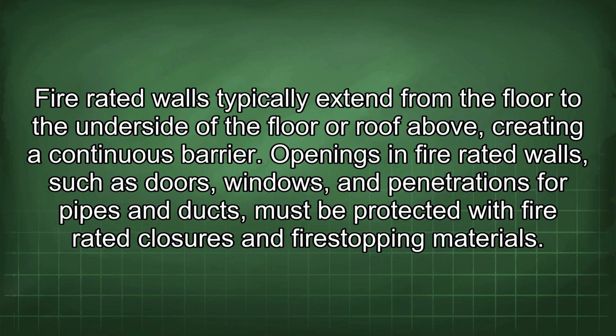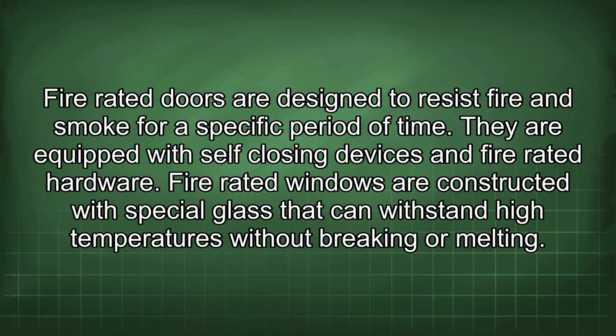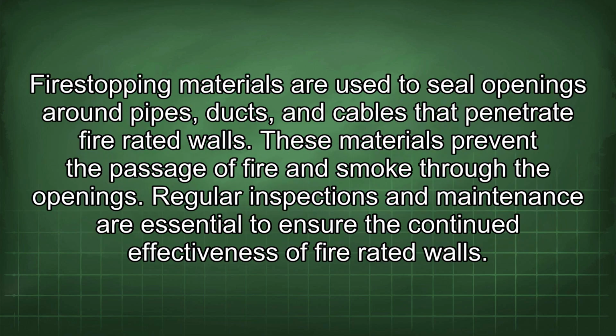Openings in fire-rated walls, such as doors, windows, and penetrations for pipes and ducts, must be protected with fire-rated closures and fire-stopping materials. Fire-rated doors are designed to resist fire and smoke for a specific period of time. They are equipped with self-closing devices and fire-rated hardware. Fire-rated windows are constructed with special glass that can withstand high temperatures without breaking or melting. Fire-stopping materials are used to seal openings around pipes, ducts, and cables that penetrate fire-rated walls. These materials prevent the passage of fire and smoke through the openings.